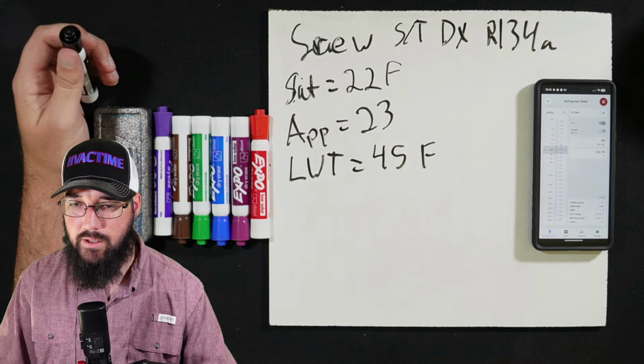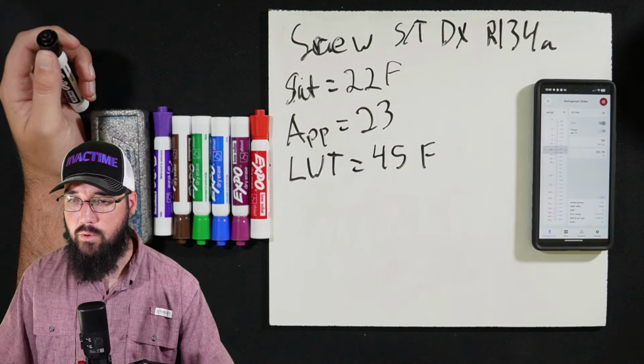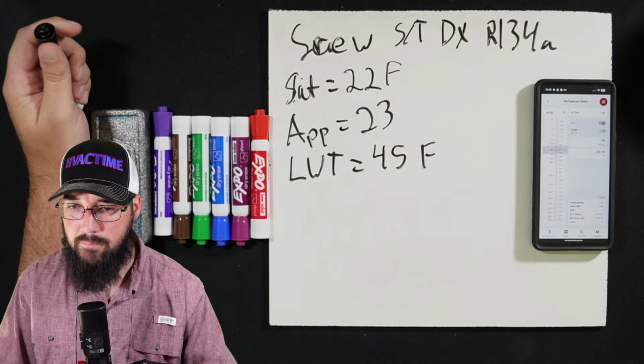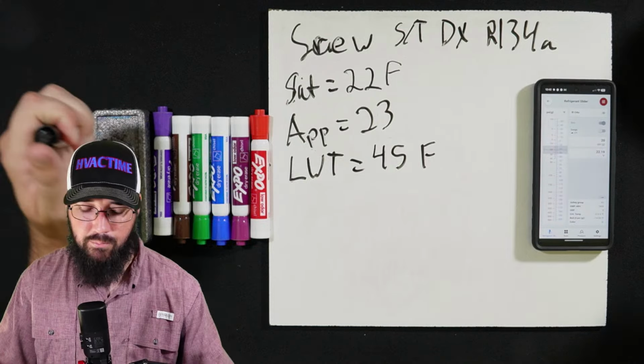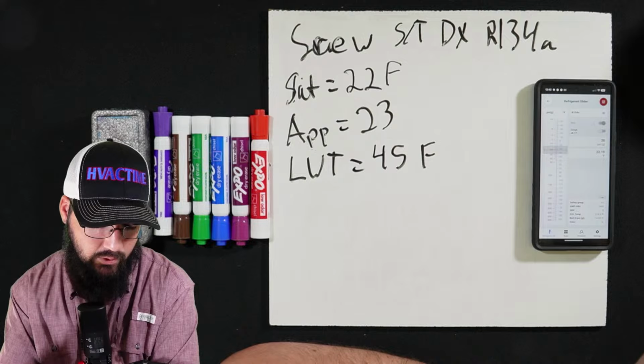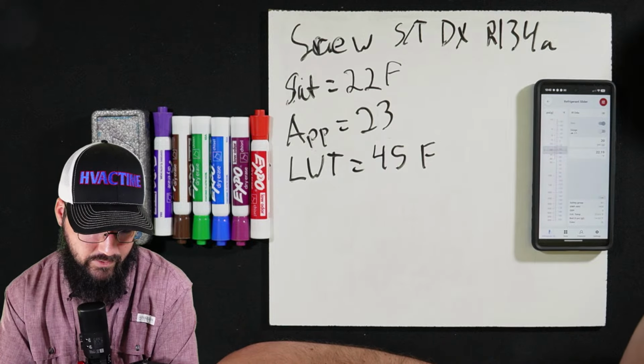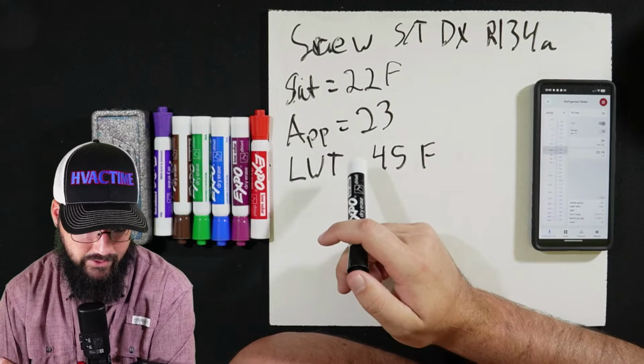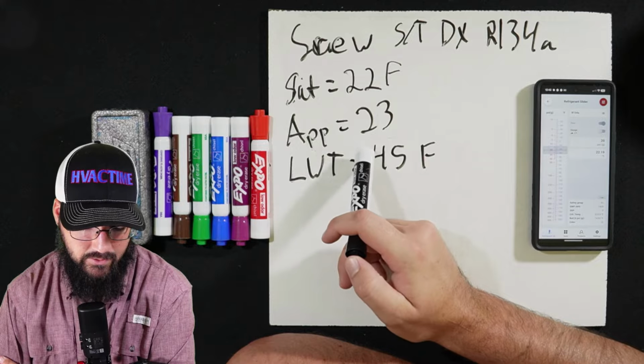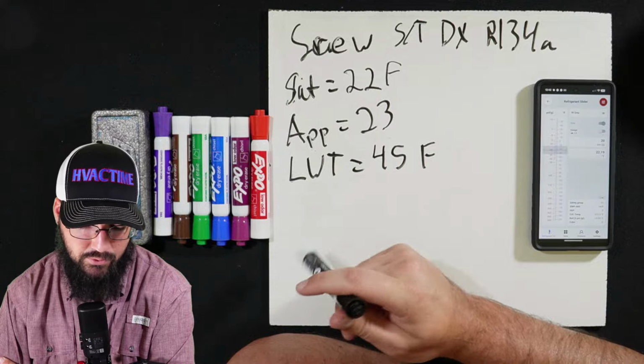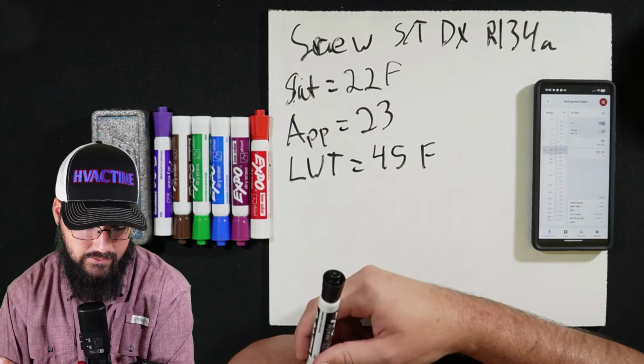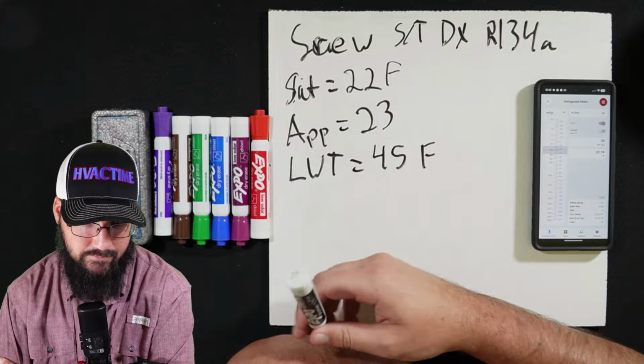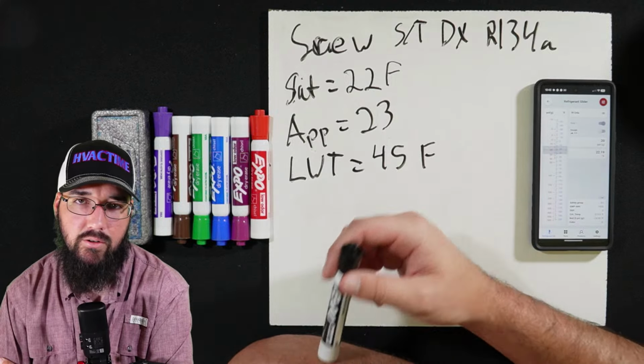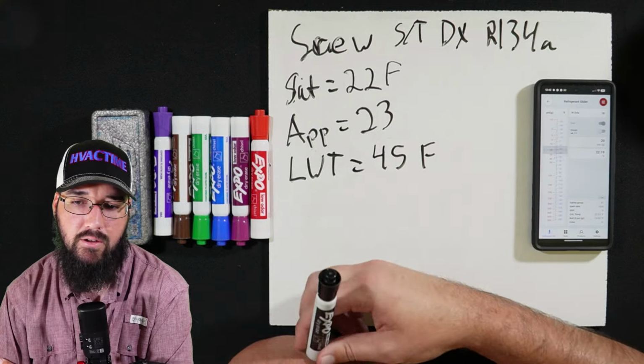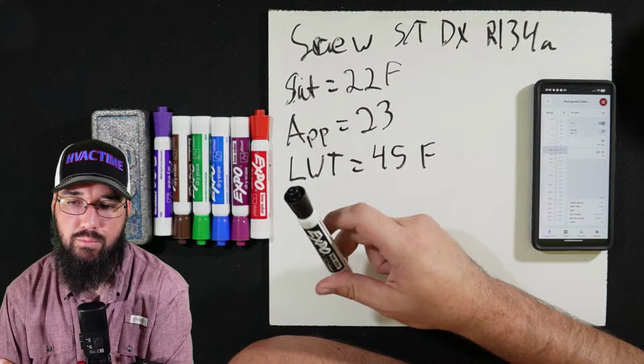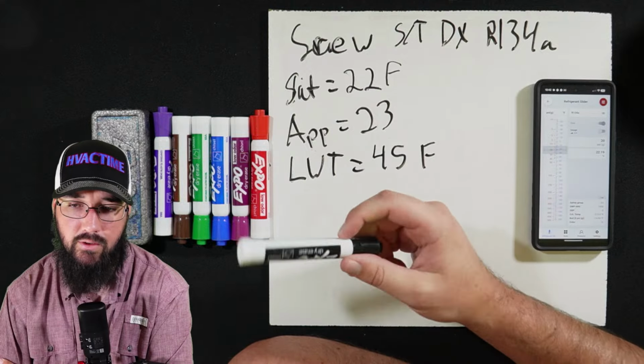yeah, so some of the guys are kind of getting on a similar page here, where we're thinking possible low water flow. So let's think through that. If we have a low water flow, the issue with low water flow is we have a really high approach value. Have you checked your DP across your evaporator? Do you know what your pressure difference on the water side specifically is on the evaporator?